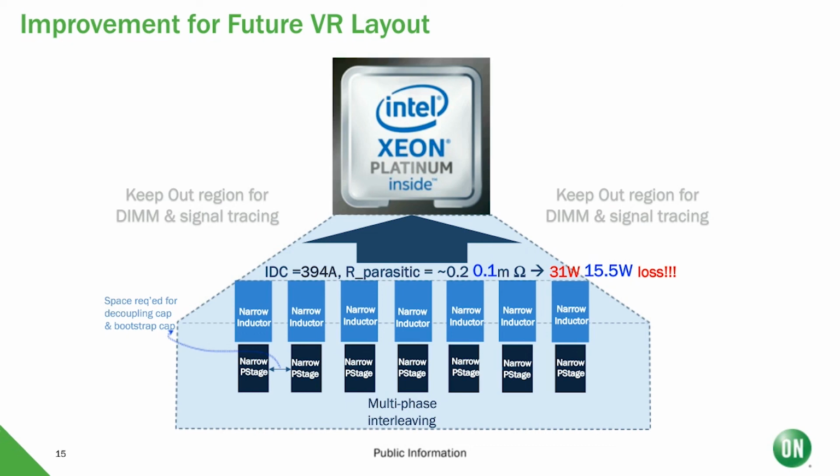So I think 5 years from now, it's more likely that we see most customers adopting a 48 volt design such that they step the 48 volt down to 12 and still continue to use today's technology to provide the core voltage to the CPU from 12 volt.